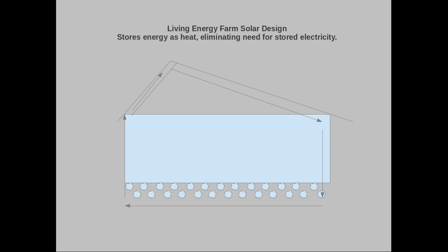You have solar collectors. If this is a south-facing roof, you generally kick the collector up to 60 degrees because remember your winter sun angle is at 30. So if you're at 90 degrees to 30 degrees, that means 60 degrees, if that makes sense. So a steep southern roof or a steep set of collectors. For fluid-based systems, you need corrosion-resistant collectors. That has come to mean copper flat plate collectors, which are quite expensive.